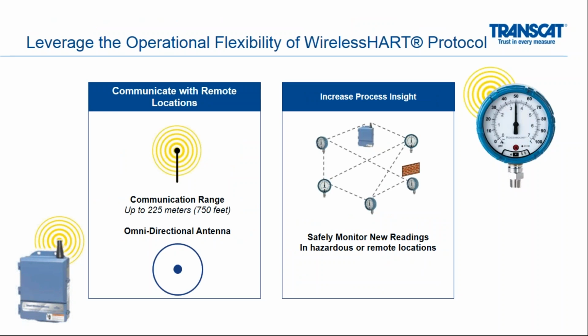And then finally, the communication for wireless is very, very robust. Not only can the communication go up to 750 feet with an omnidirectional antenna, the way WirelessHART works is they can bounce off of each other. It is a mesh network. In the picture on the right, you see what's supposed to represent a brick wall. If at any point in time a brick wall got between one gauge and another gauge, those gauges would find a new way around to ultimately get back to the gateway. So not only is the gauge reliable in its local reading, but its wireless network is also incredibly reliable and robust because it really can't get disconnected. There's always a new way to get back to that gateway.